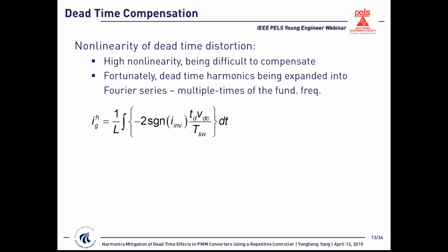According to the above analysis, we have known that the dead time distortion is highly nonlinear, as shown in this equation. We can further summarize that the injected grid current is affected by the inverter output current polarity, the dead time duration, the switching frequency, and the DC link voltage.